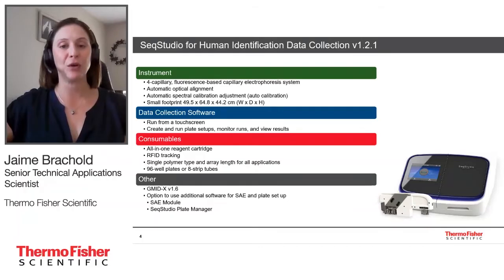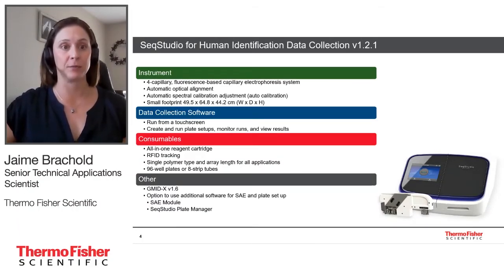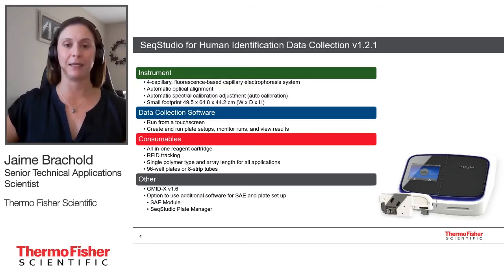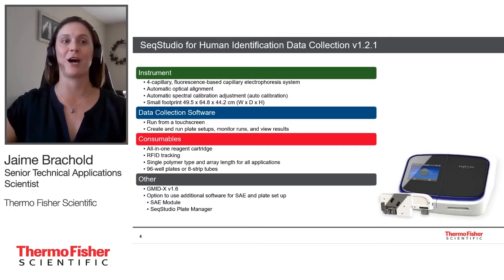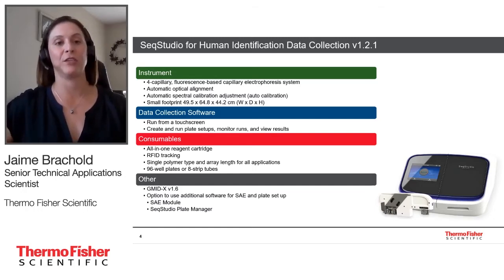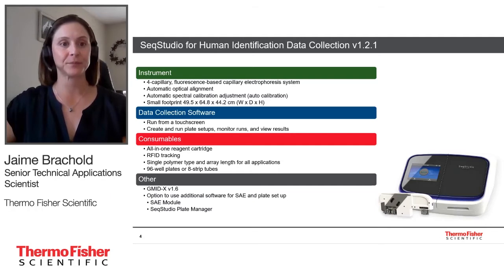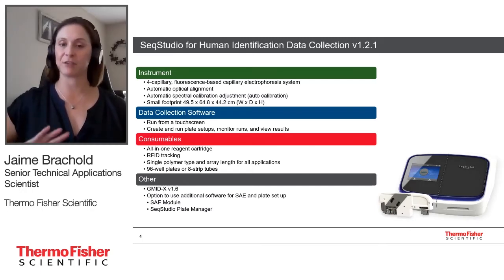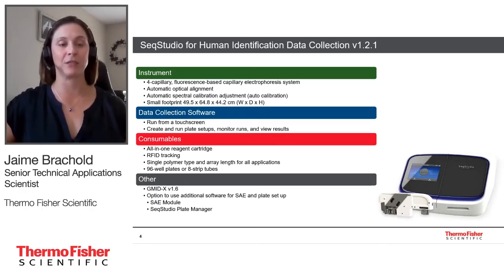Now talking about the SeqStudio, which is our newest CE instrument — for those that don't know, it is a 4-cap CE instrument. A couple of ways you're going to save time: there is an automatic optical alignment, meaning that when the capillary is installed, the spatial is automatic with no need to run it manually. There's also an automatic spectral calibration adjustment, also called auto-calibration. You only need to set up a spectral one time for each dye set on the instrument, and after that, you don't have to run a manual spectral calibration again.